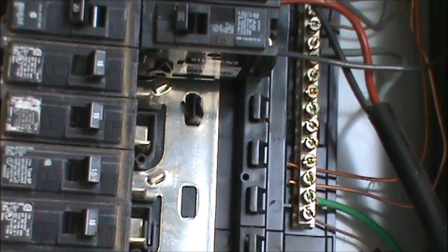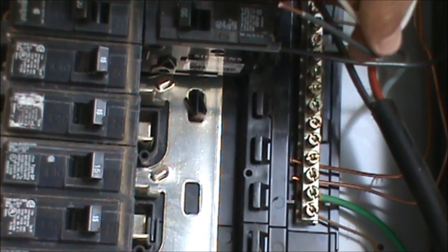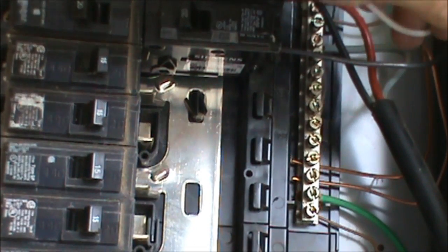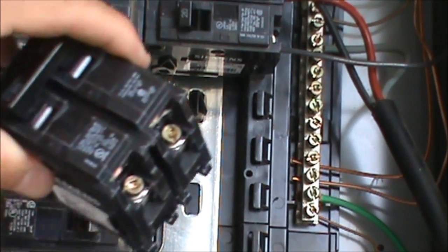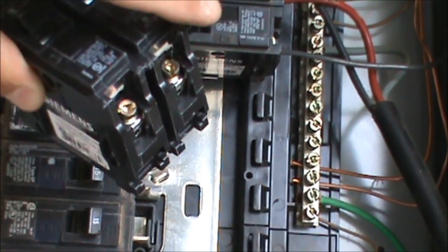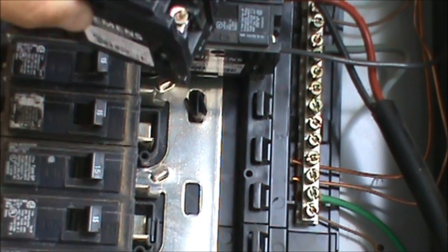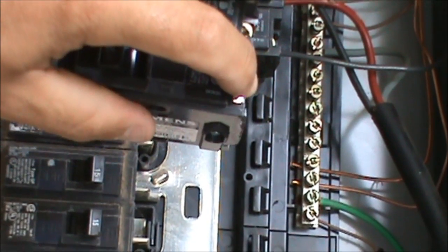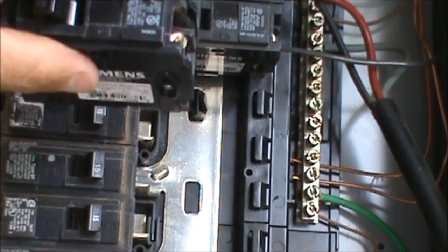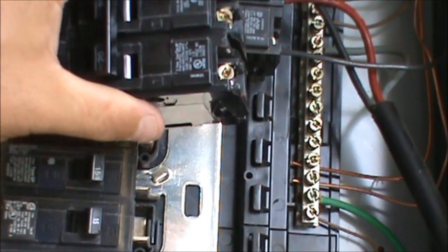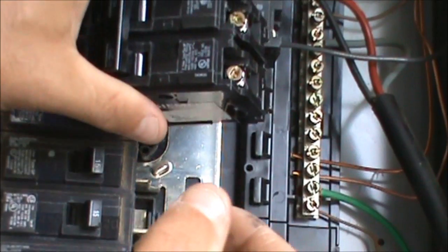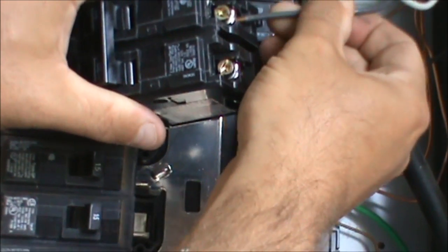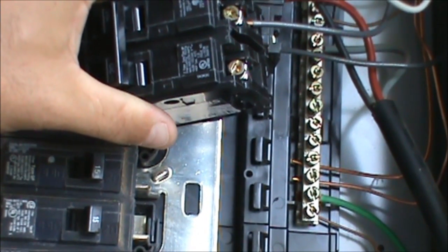I've routed my two wires basically to where they need to go. There's a black wire and a white wire left, so you have your hot and your common wire. What we're going to do is attach those wires to these two screws on our double breaker. It really doesn't matter which wire goes to which screw - they're both going to be hot - but generally I usually put on the top screw the hot wire and on the bottom screw the common wire. So all you have to do is insert the wires in here like this and then tighten up your set screw.